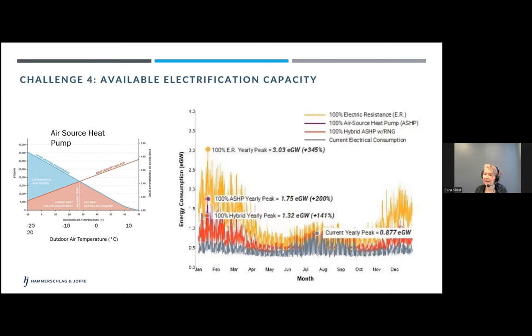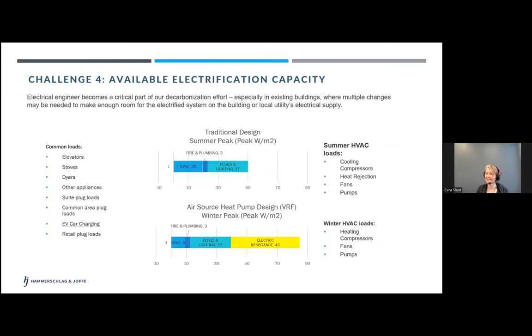So as MEP practitioners, on a building by building basis, having air source heat pumps that can operate to minus 18 and then turn on a backup system is acceptable, but at a grid level, it's not going to work. So we need a strategy as an industry to figure out how to deal with this.